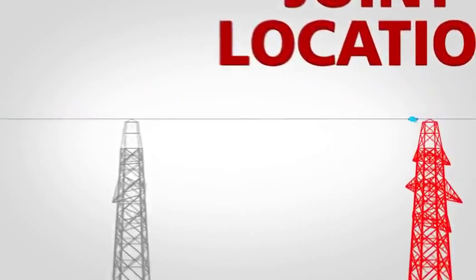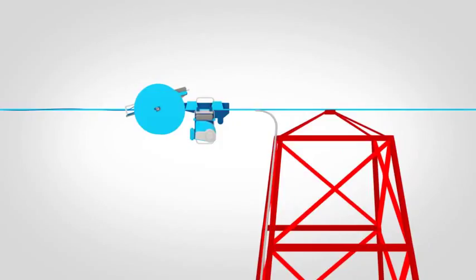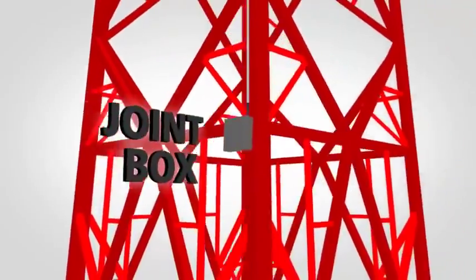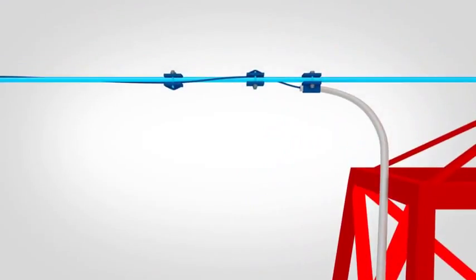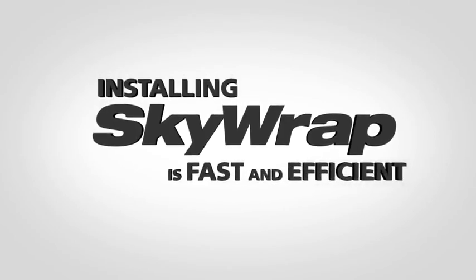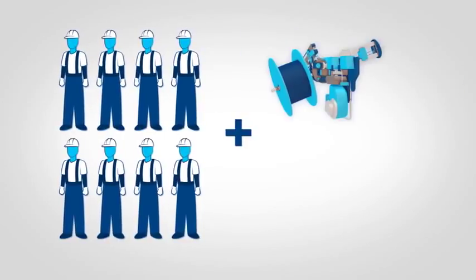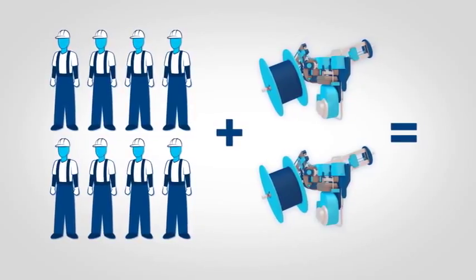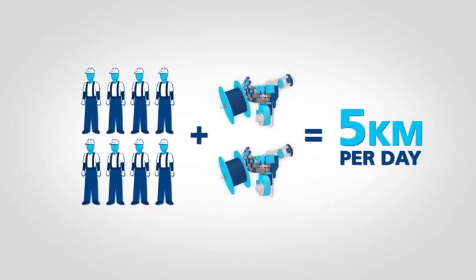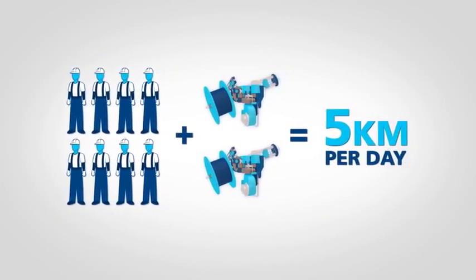Once the final joint location is reached, the remaining cable is clamped securely to the conductor and fed through a conduit that leads down the tower to a joint box. The upper end of the conduit is attached directly to the conductor, ensuring the Skywrap cable is completely protected. Installing Skywrap is fast and efficient. Eight linesmen and a pair of wrapping machines can cover distances of up to five kilometers per day, minimizing your investment.